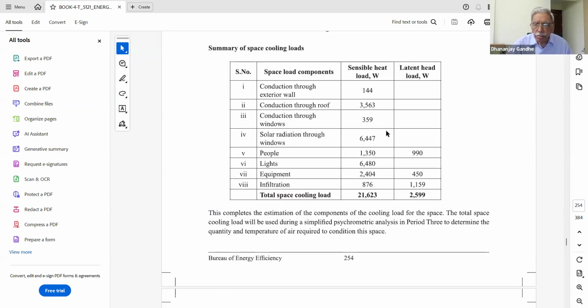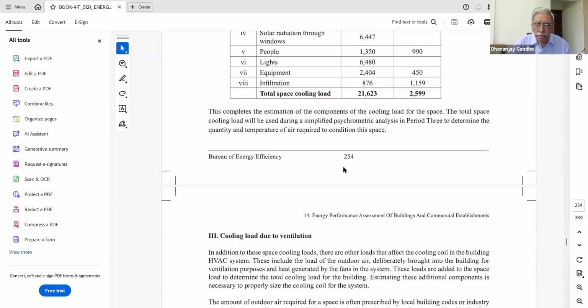And then infiltration air is also mentioned. Equipment load is also mentioned here. Now there is the equipment latent heat and infiltration latent heat. These calculations can also be worked out as per the procedure, and this is the summary. So the summary of cooling loads in this particular space is: sensible heat load is 21,623 and latent heat is 2,599. So these figures are to be used for performance assessment of that system.